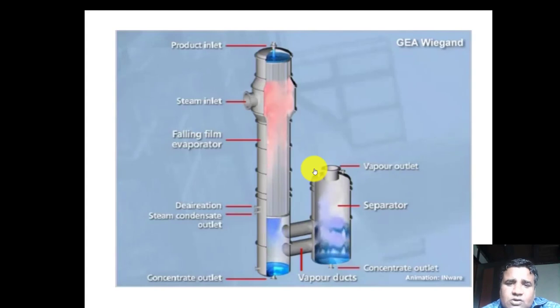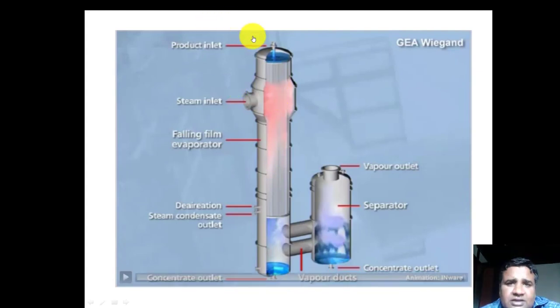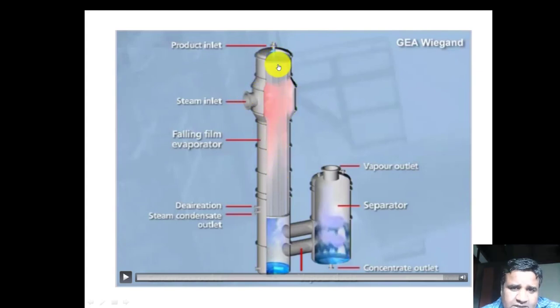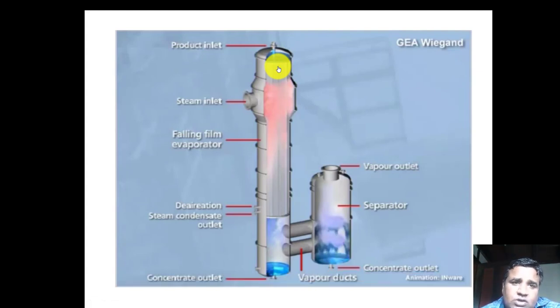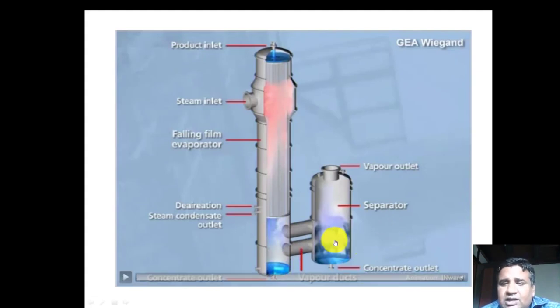The concept is clear: in the rising film evaporator the product moves from bottom to top because heating converts it to vapor and the vapor rises due to density difference and pressure difference. Here in the falling film evaporator the condition is different — we allow the product to fall from the top under gravity. Steam circulates outside the tube, transfers heat, and by the time it reaches the bottom it is a mixture of vapor and concentrated product. From the bottom we can collect the concentrated product and the vapor from the separator.